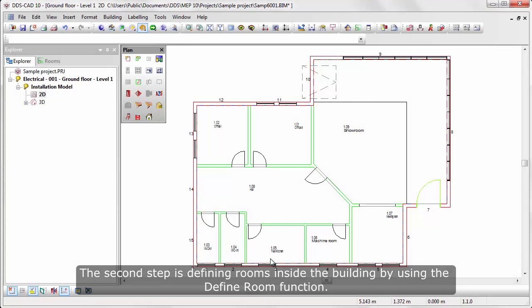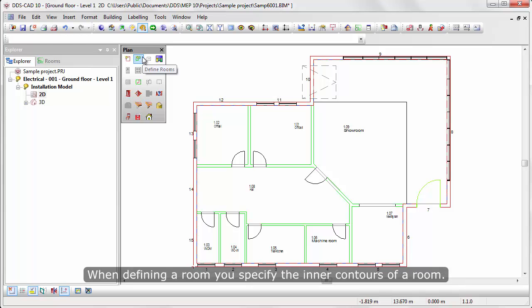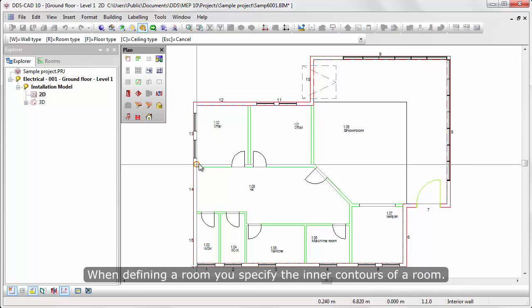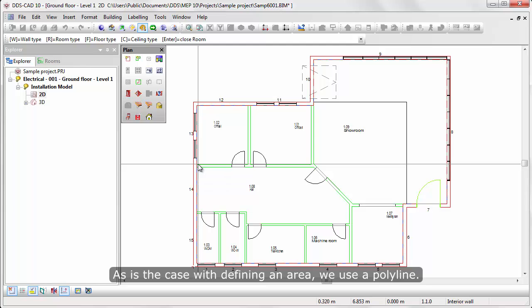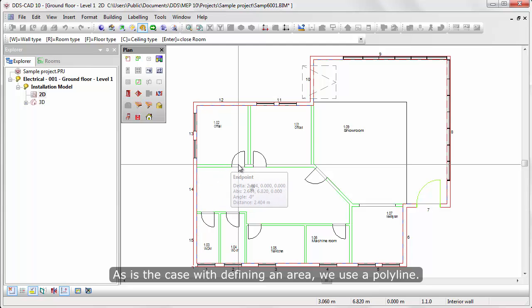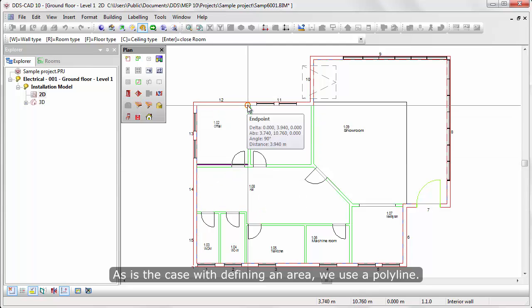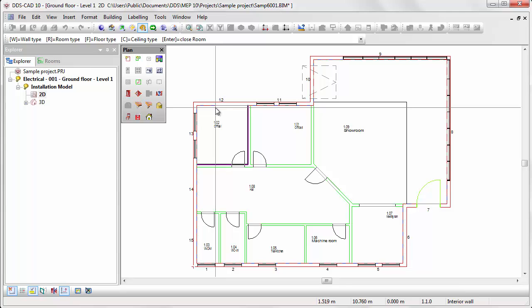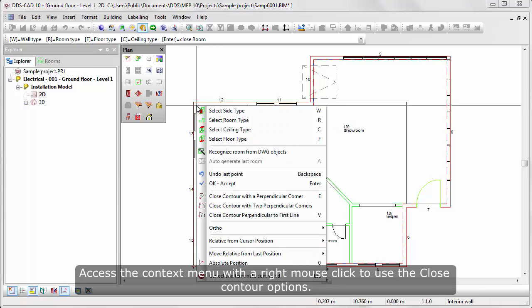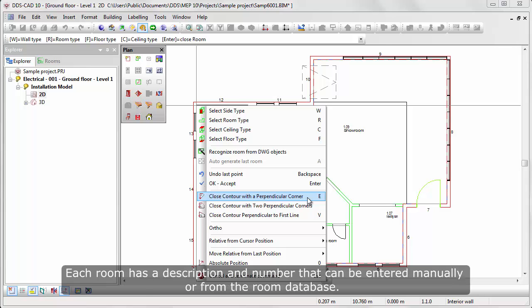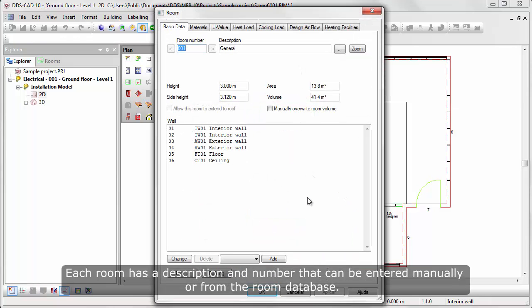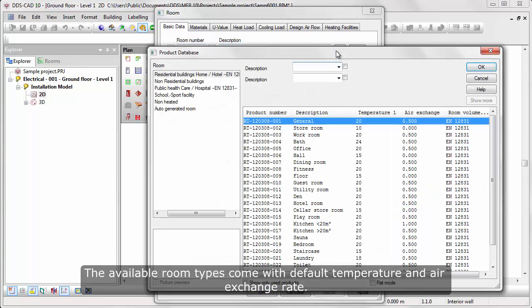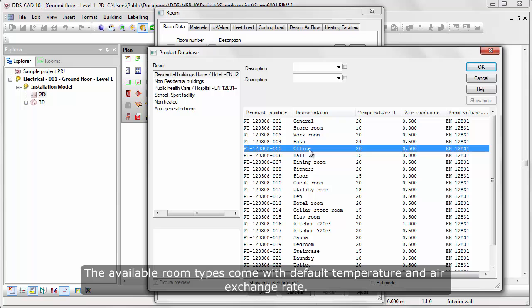The second step is defining rooms inside the building by using the define room function. When defining a room, you specify the inner contouring of a room. As is the case with defining an area, we use a polyline. Access the context menu with a right mouse click to use a closed contouring option. Each room has a description and number that can be entered manually or from the room database. The available room types come with default temperature and air exchange rate.